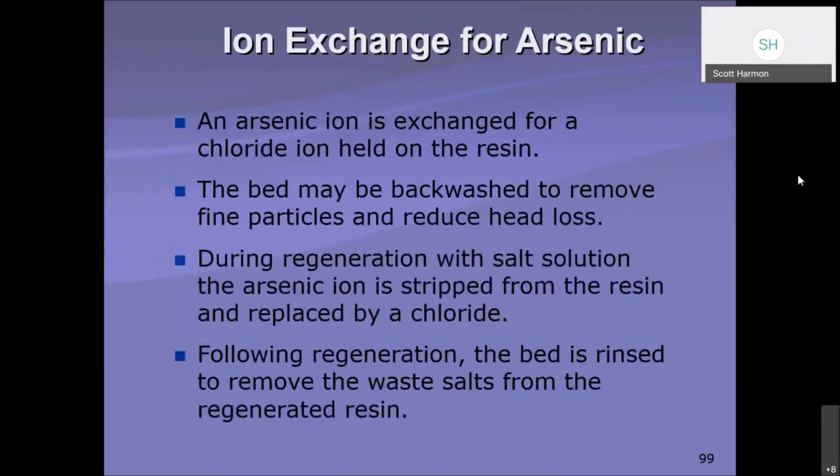So if we're talking about it, sorry about the cough, guys. We're talking about ion exchange for arsenic in particular, an arsenic ion exchange for chloride ion held on the resin. So it's essentially adhering to a chloride particle. The bed may be backwashed to remove those particles and reduce head loss. So very typical filtration type things.